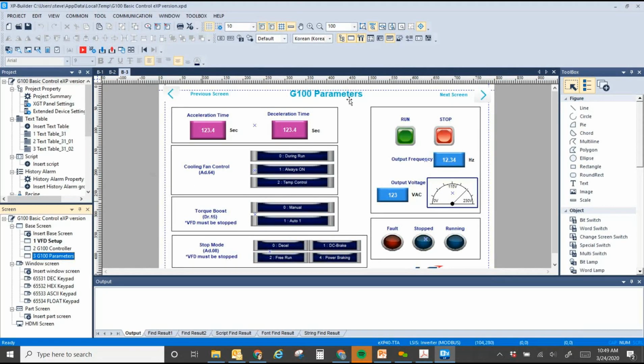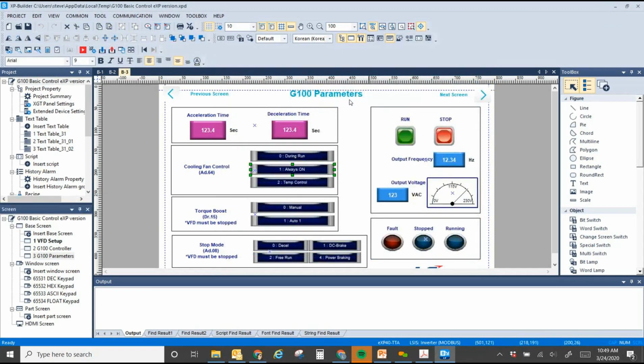So that makes it pretty easy to find stuff. Let me click the last page here. This is a direct answer to your question: can we read and write parameters? Yes, we can. This is showing the parameter for the cooling fan, AD64. You could click 0, 1, or 2 to turn the fan on, off, or only on during temperature control. If you click this, you can see it's actually taking a word and writing a number to that word set, which is an address.